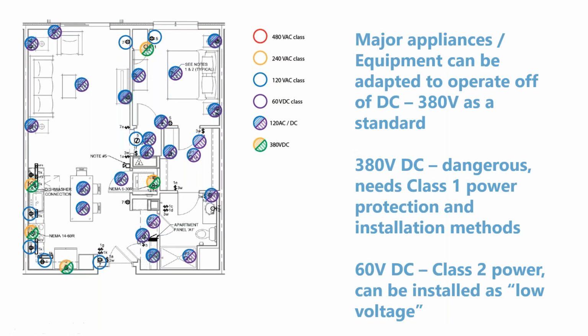When we look one step further and at the appliances that typically dictate the largest amount of power demand in a residential unit, and that we typically supply with 240 volt AC, higher voltage class power, the majority of the appliances that you purchase today or you specify on a project actually are DC driven inside. And that's something that's happened over the last 20 years as appliances go towards more of a smart appliance configuration that have additional digital controls that use inverter technology and that have basically put all of the power distribution within the appliance on the DC side. So again, the potential exists to replace those 240 volt AC appliances with what is somewhat becoming the standard of a 380 volt DC topology.